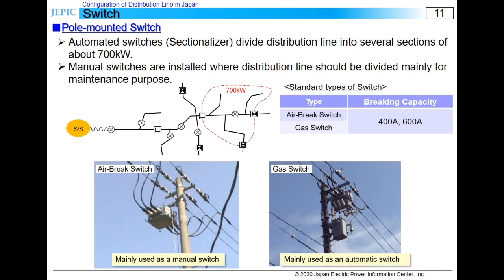Automated switches are installed so that each section divided by them has a certain demand, and where a manual switch should be installed is decided considering the maintainability of the distribution line. For example, the place that's considered to be effective for power outage recovery, or a branch point of a long branch line. Where and how many switches should be located is closely related to the number and duration of power outage customers in an outage. So I think that's an important point to improve SAIFI and SAIDI. Switches can turn on or turn off electricity supply, so it's also important to prevent power outage due to wrong operation of switches.